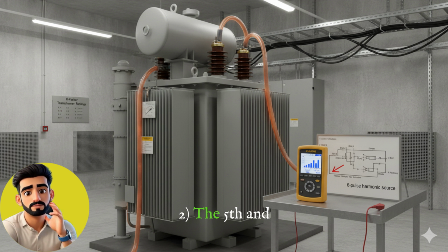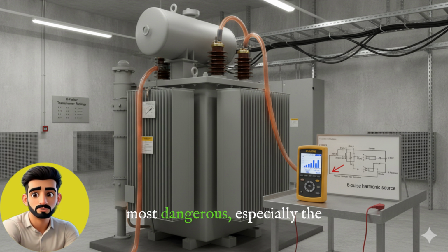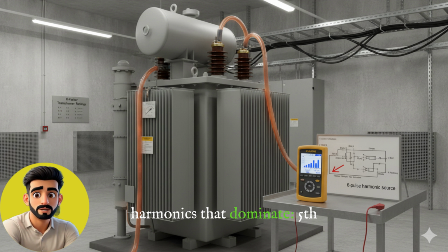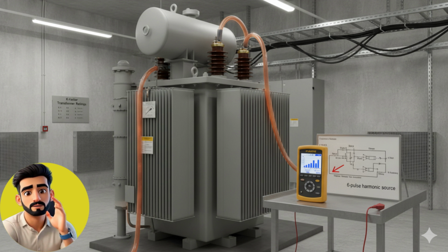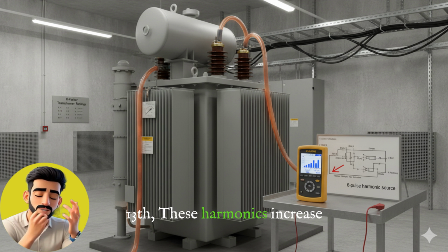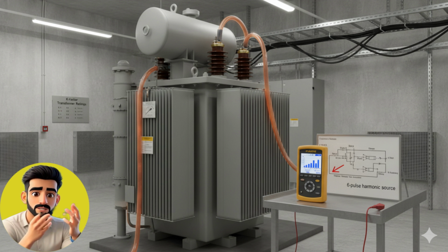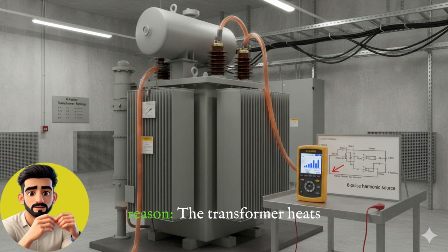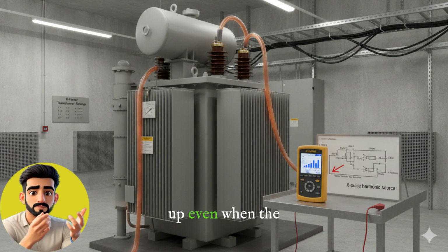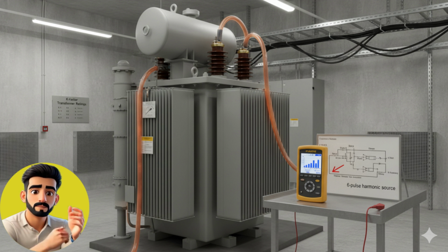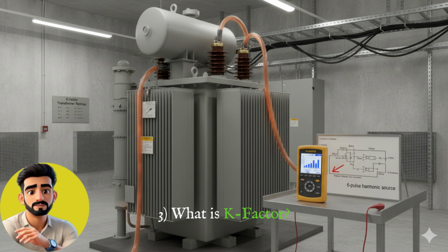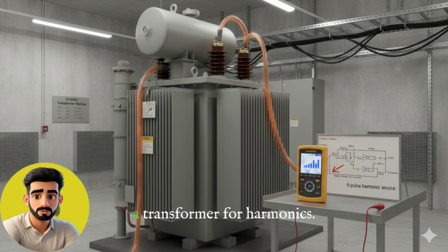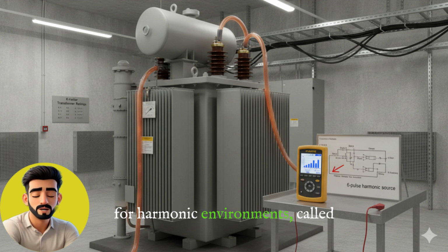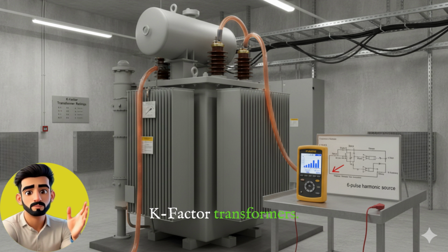2. The 5th and 7th harmonics are the most dangerous, especially the harmonics that dominate: 5th harmonic, 7th harmonic, 11th, 13th. These harmonics increase eddy current losses multiple times. And this is the reason the transformer heats up even when the load is normal. 3. What is K factor? The fitness rating of a transformer for harmonics. Special transformers are used for harmonic environments, called K factor transformers.